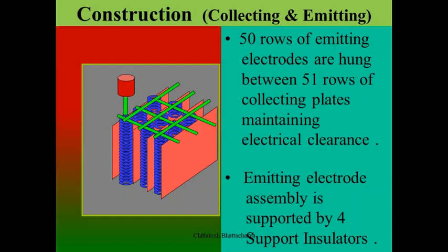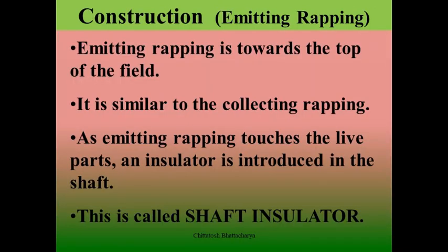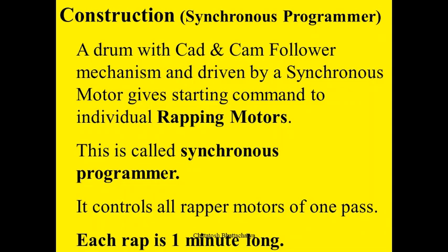Each helix is 4.5 meters long; one column consists of three such helixes vertically connected, and each row has sixteen such columns, with 50 rows. These 50 rows of emitting electrodes are hung between 51 rows of collecting plates, maintaining the required electrical clearance. The emitting electrode assembly is supported by four support insulators, and there is a rapping arrangement fitted with hammers placed across the collecting plates, mounted at different angles to rap at different times, maintaining a rapping sequence by rotating a connected shaft.